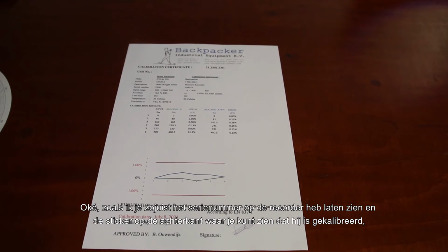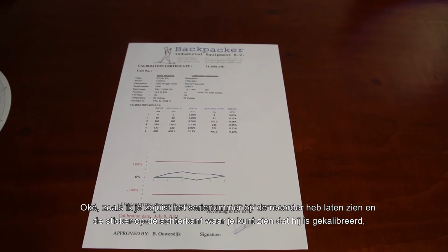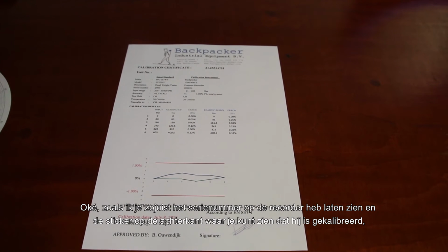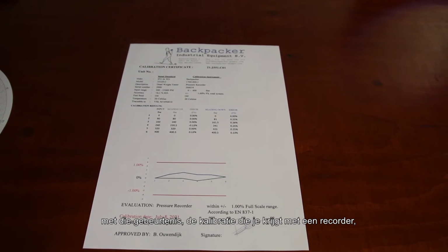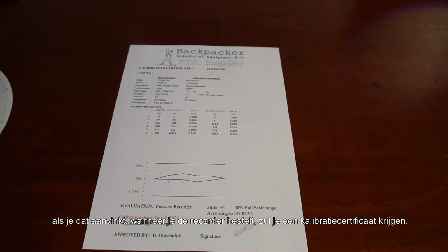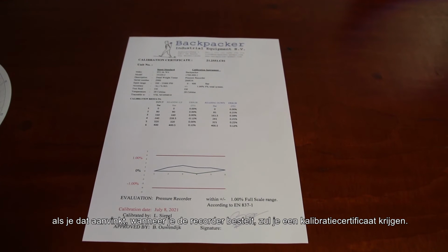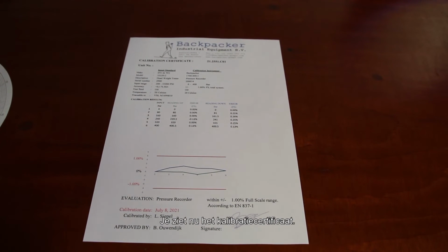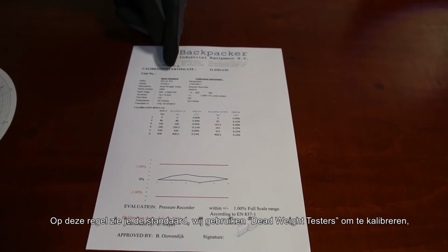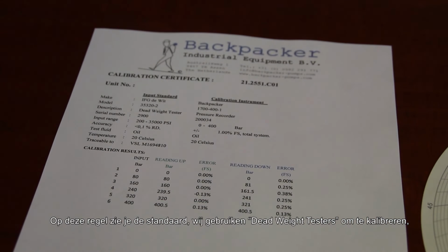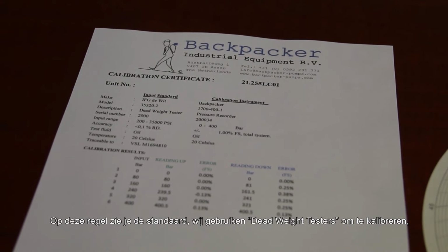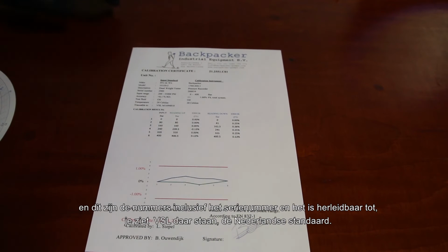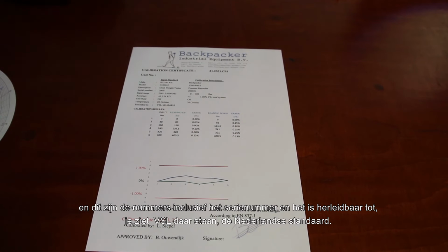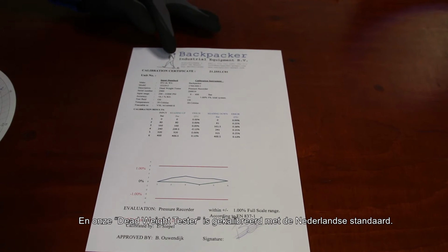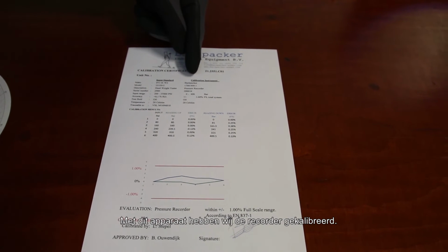As I just showed you the serial number on the recorder and the sticker on the back where you can see that it's been calibrated, when you order a recorder, you will get a calibration certificate. You now see the calibration certificate. On this line you'll see the input standard, that is, the deadweight testers we use to calibrate. And this is all the numbering, the serial number, and it's traceable to, and you will see VSL, that's a Dutch standard. And our deadweight tester is calibrated against the Dutch standard. With this tool, we calibrated the recorder.